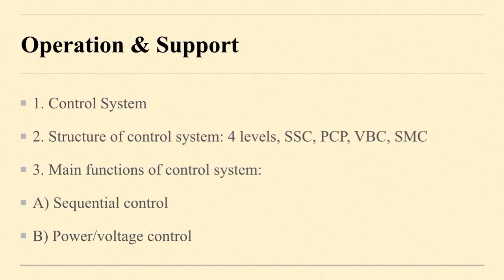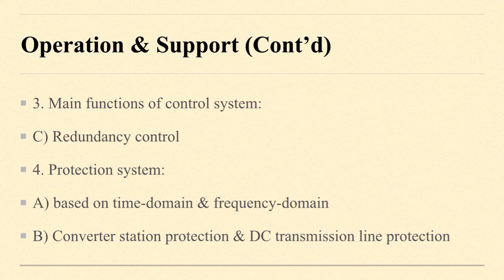Next is power or voltage control, active power integrated control, and reactive power integrated control, and VF integrated control, DC voltage control, control mode selection or switching, 5 kinds of power control. And next is redundancy control. When faults are found, each control system switches redundant systems in time so as to ensure that the whole system is always in working state.